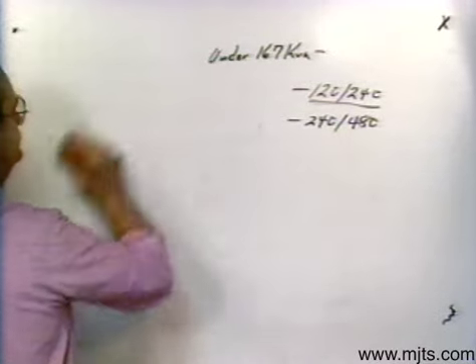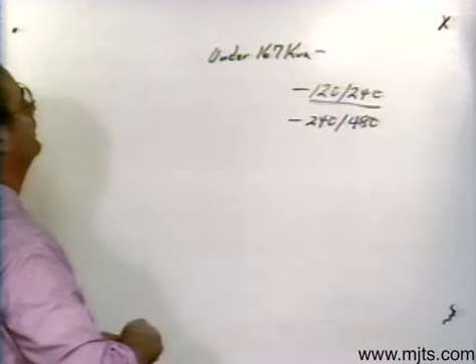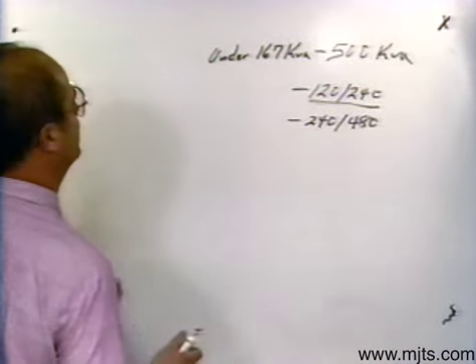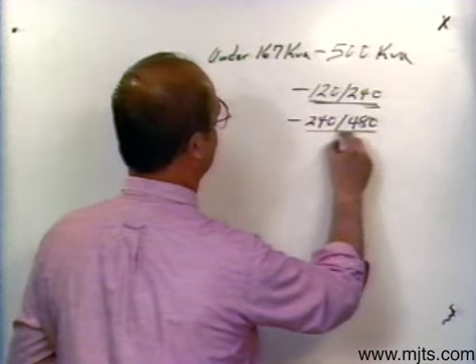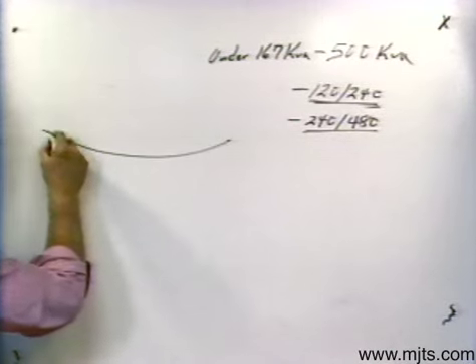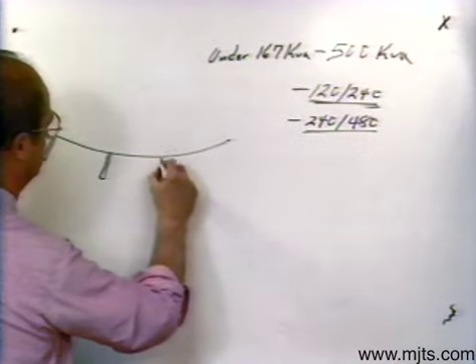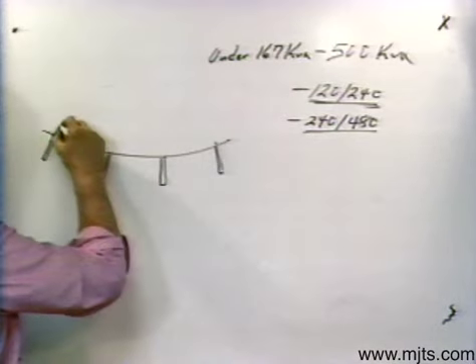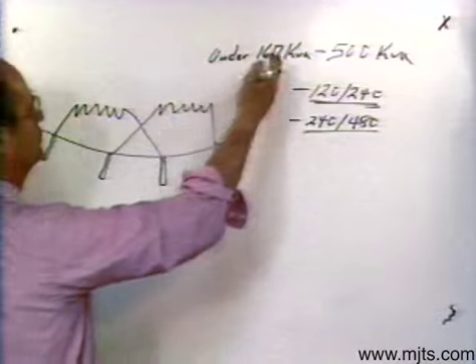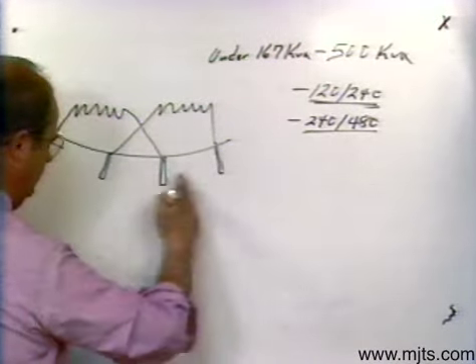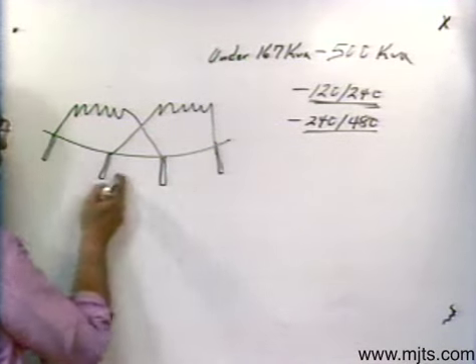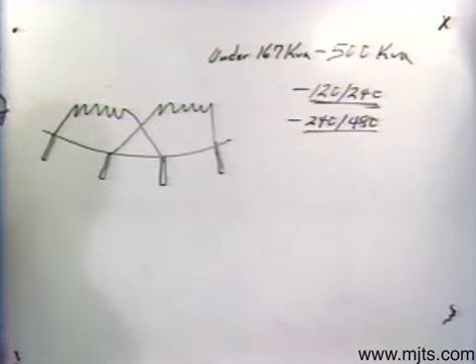If we have a transformer rated anywhere from 167 through 500 kVA, with a low side rating of 120/240, then you are going to have a 4-bushing transformer. The way that looks, it will have spade lugs with NEMA hole spaces in the lugs. You will still have the possibility of being series or parallel connected, but because of the high current-carrying capacity, instead of having small connections on the back side of the bushings, you make your connections on the outside. There are no internal connections.